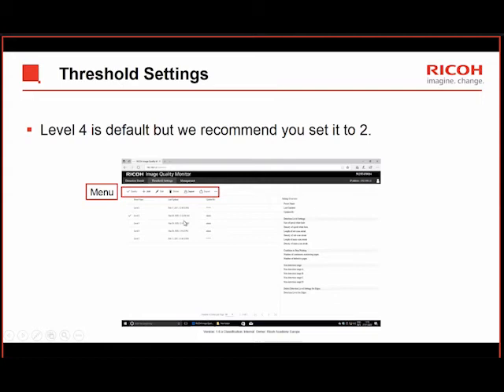Japan has set the default with 5 threshold settings here, level 1 to 5. 5 is the strictest - if you get a very minor fault, level 5 will pick it up and show an error. Level 4 is the next one down, and level 1 is the loosest, the most flexible. By default, Japan sets this to level 4, so fairly strict.